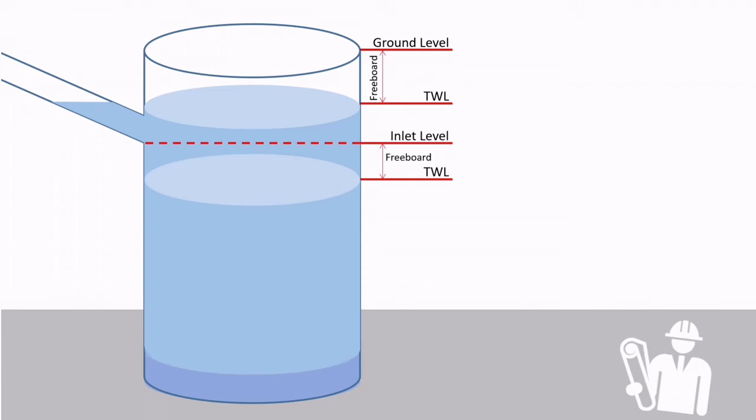Not every wet well requires this, however in certain situations the next level to be considered is the emergency storage volume, which tends to be based on a set time to allow the pumps to be out of operation. So as an example, if you have an average incoming flow rate of 0.5 cubic meters per hour and you believe that two hour emergency time is suitable to install replacement pumps or repair the pump unit, then you will need a cubic meter of emergency storage.